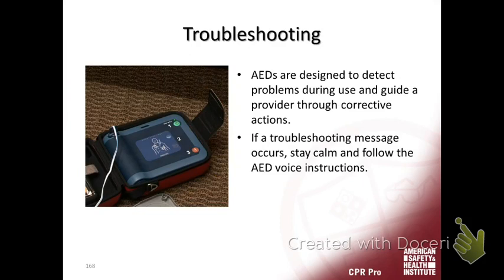If you start having trouble with the AED, most of the time the problem is the cables aren't plugged in correctly. The other issue is the battery — poor maintenance may mean the battery isn't charged, and you can't do much about that. If it's not working, step back, look at it, think about it, and restart the process. Unless something's wrong with the machine itself, you can more than likely figure it out.